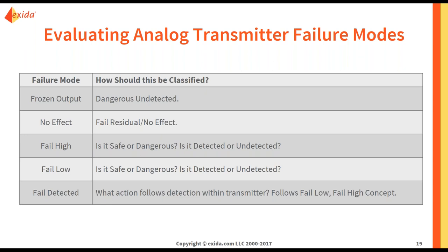The ones that we are unable to classify without knowing your system are fail high, fail low, and fail detected. For fail high, we don't know if it is safe or dangerous, detected or undetected. The same with fail low. With fail detected, your transmitter detects that you have an internal failure and it is driving your output either high or low, just like a fail high or fail low might. It follows the same concept depending on how you configure your system.